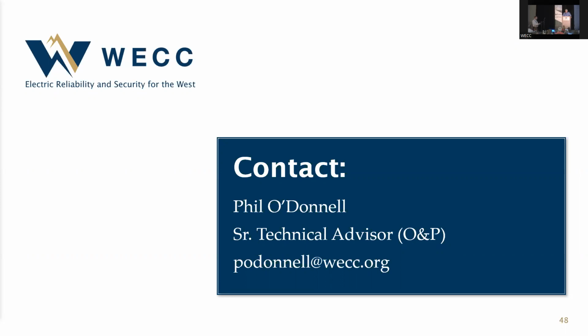So I'm trying to think of a question. If you're saying that when I said nameplates are the gold standard, that's what we like because it's pretty clear. It's definitely manufacturer's documentation. So you do have to set your facility rating to respect the most limiting component. If you've got a 1200 amp limit on a circuit breaker, you can't set your facility rating greater than 1200 amps unless you do some kind of analysis that can overrule that nameplate rating.